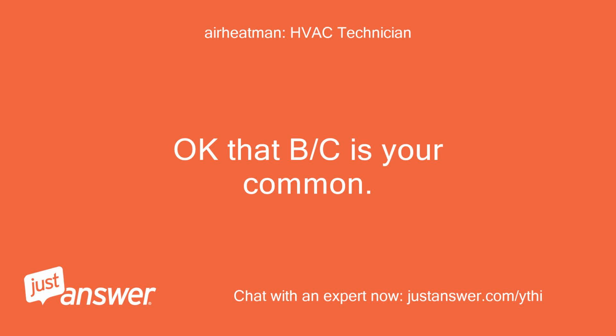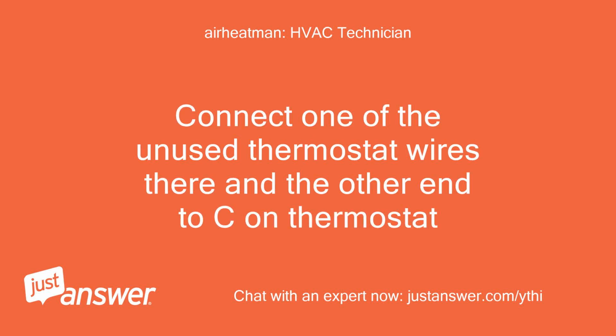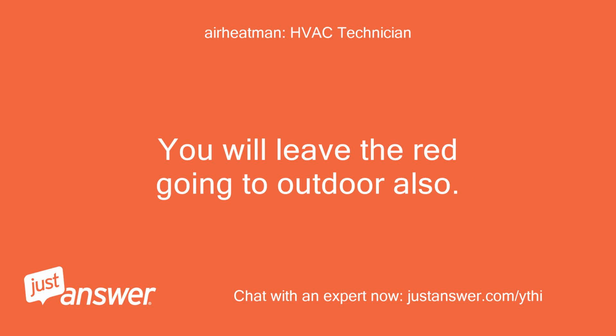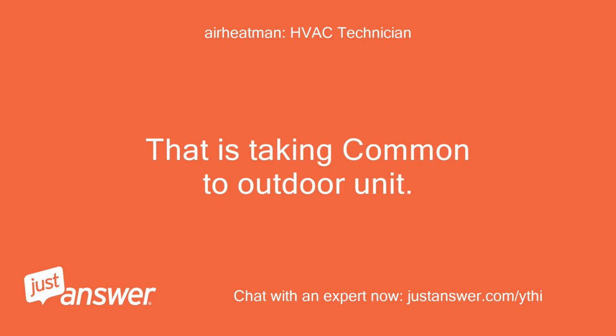Okay, that BC is your common. Connect one of the unused thermostat wires there, and the other end to C on the thermostat. You will leave the red going to the outdoor unit also. That is taking common to the outdoor unit.